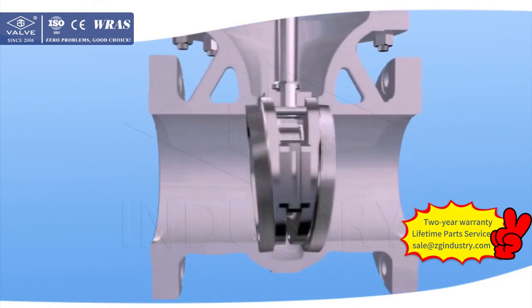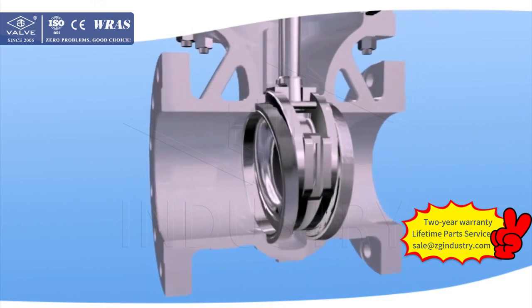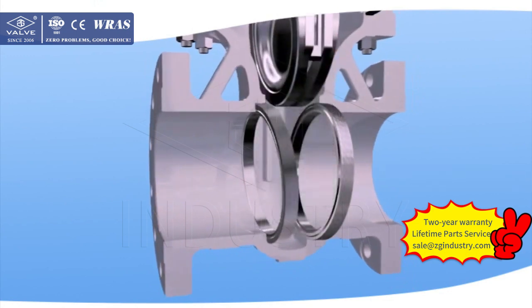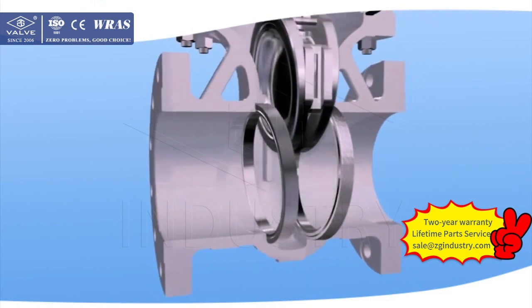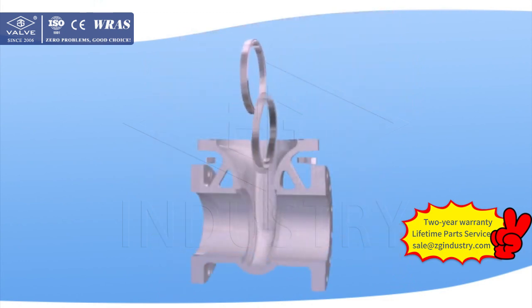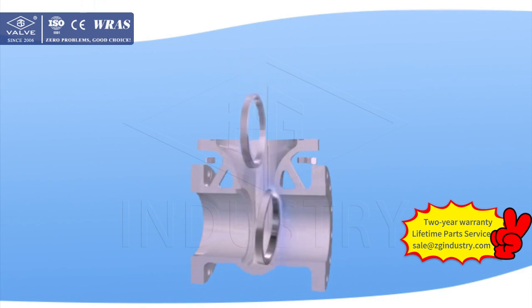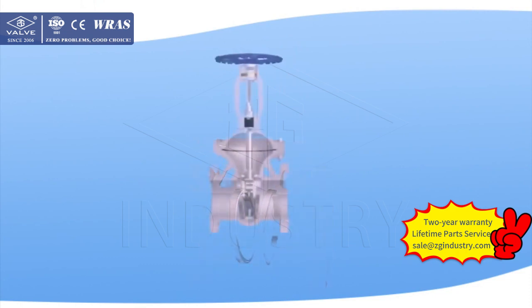2. Full carbon material valve. The seat is forged, high density, with good sealing capacity. The sealing face uses 13 Cr or Stellite hard alloy material. Overlay net thickness is over 2 mm. The valve seat is threaded or welded on the valve body, easy to maintain and assemble.